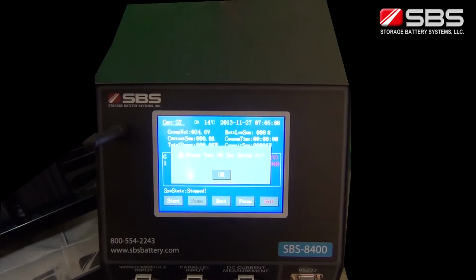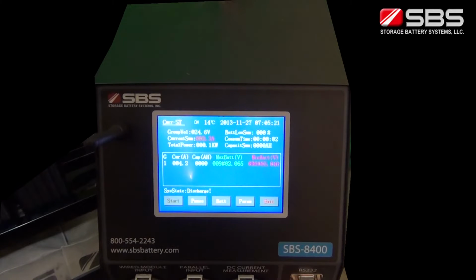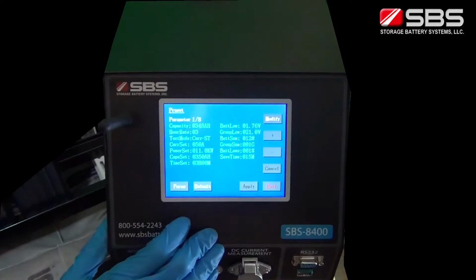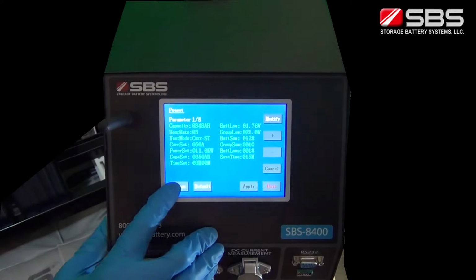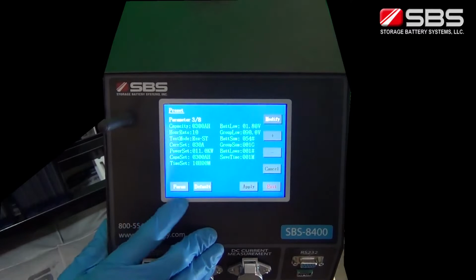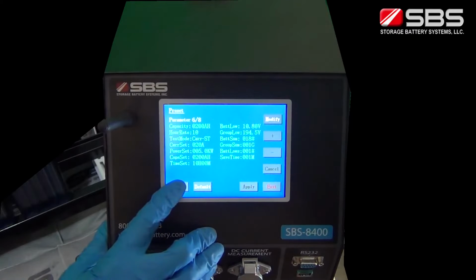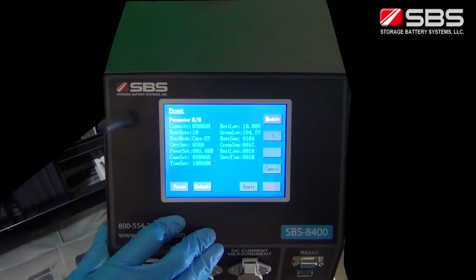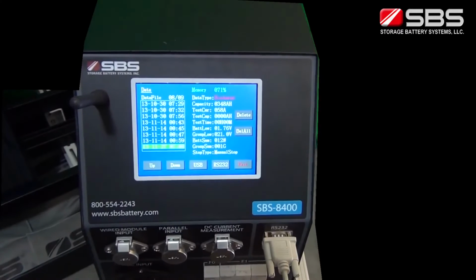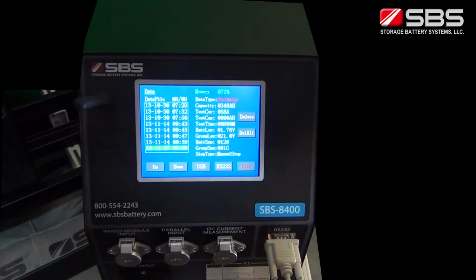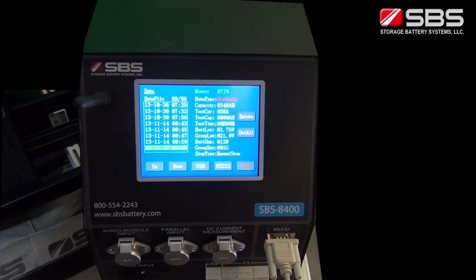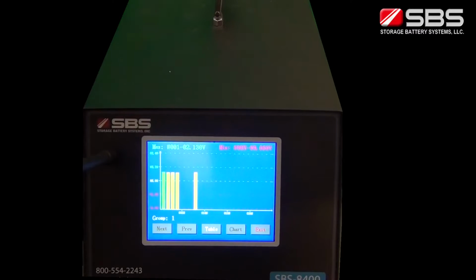Follow the commands on the screen to connect the load to the batteries and initiate the test. You may manually stop the discharge by pressing Pause to pause the discharge, or Stop to end the discharge. Pressing Start will continue the discharge. Pressing Param during the discharge will allow you to change parameters if needed. Now that the discharge testing is done, we'll review the testing results. Now we will demonstrate the real-time data feature of the SBS-8400 with a direct feed to a computer connection.